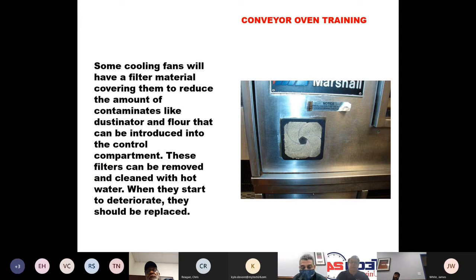Some cooling fans will have a filter material covering them to reduce the amount of contaminants like dustinator. Dustinator, if you've ever worked at a Papa John's, is a very fine cornmeal product they use to roll out their dough when they're making pizzas. It gets into the air very easily and will suck into these filters and clog them. And this also will create high temperatures in your control compartment.